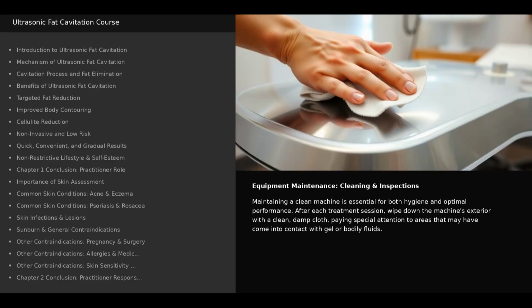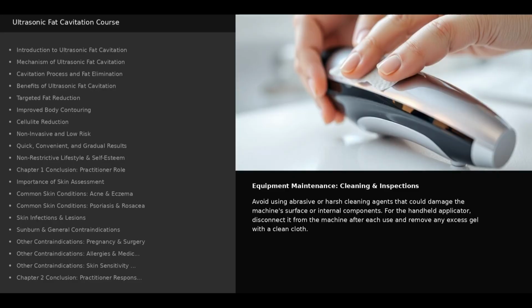Equipment maintenance, cleaning and inspections. Maintaining a clean machine is essential for both hygiene and optimal performance. After each treatment session, wipe down the machine's exterior with a clean, damp cloth, paying special attention to areas that may have come into contact with gel or bodily fluids. Avoid using abrasive or harsh cleaning agents that can damage the machine's surface or internal components.